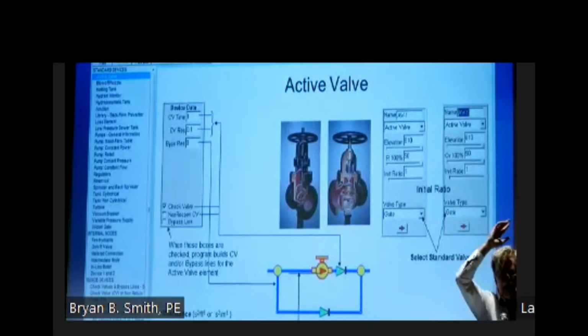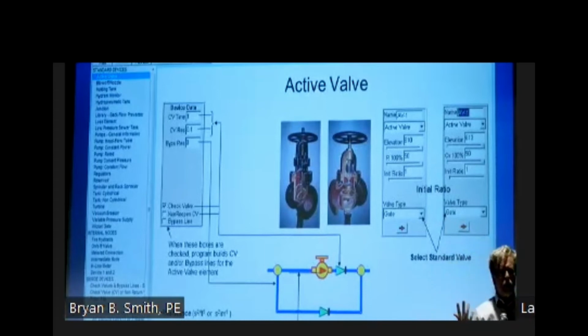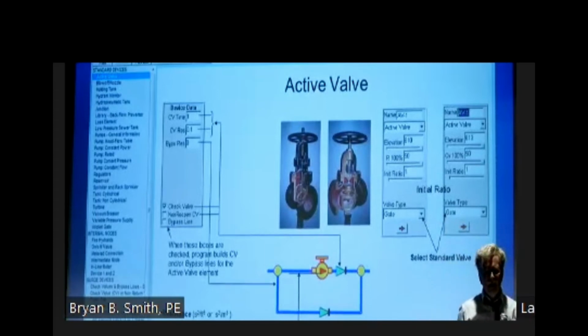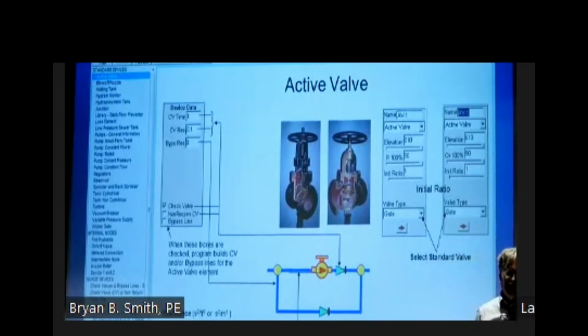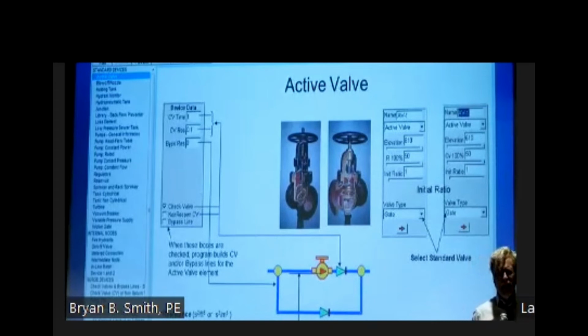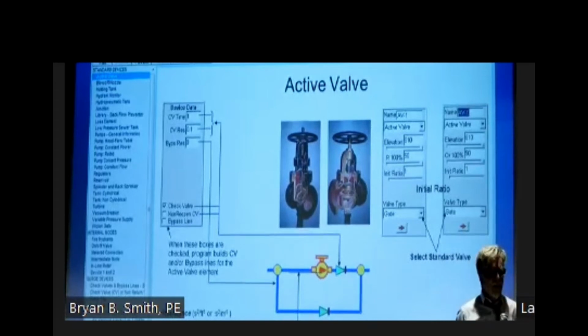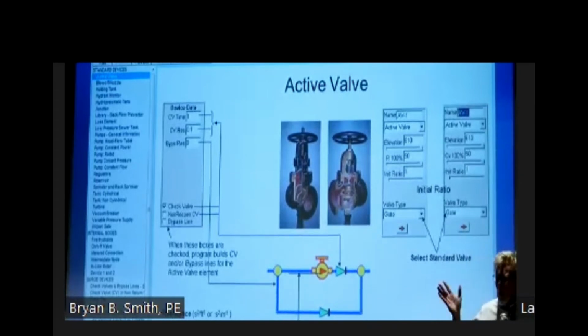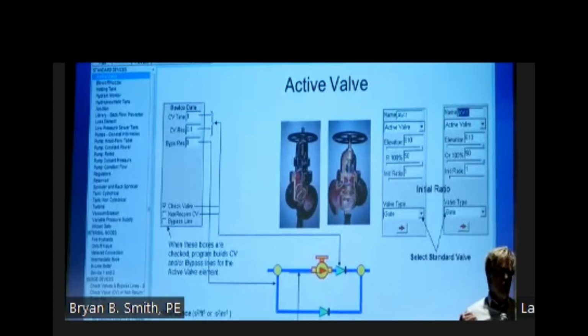Well, that's another parish, but it's close to here. Big chemical plant, uses a lot of our potable water. And our pressure is only like 40 PSI down there. So they have a booster pump, right? So they're in there taking 1,000 gallons a minute of our water, and life's great. They're a great customer. We make a lot of money off of them. It's really good for us, except for when they turn off their pump.